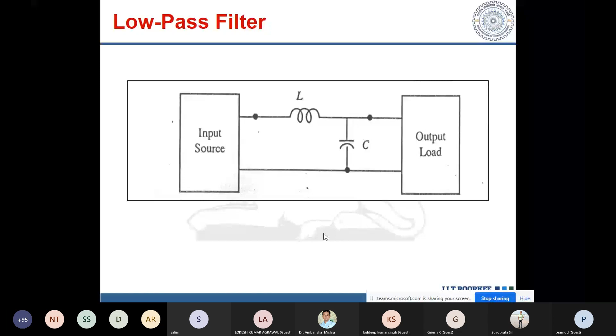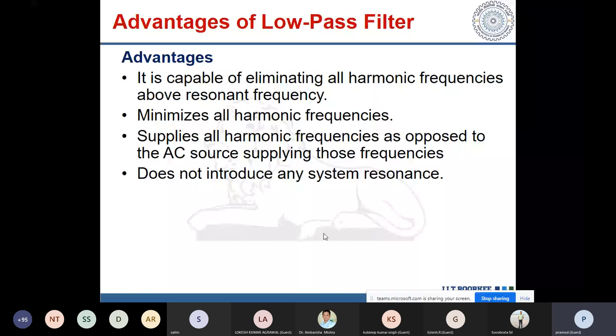You can have a simple low pass filter also. It eliminates all harmonic frequencies above the resonance frequency, that cutoff frequency. No harmonic resonance is introduced by this. It's a low pass filter. Its characteristic is like this. It does not import harmonics from other sources, but it handles the entire rated current because that inductor is in series with the load.